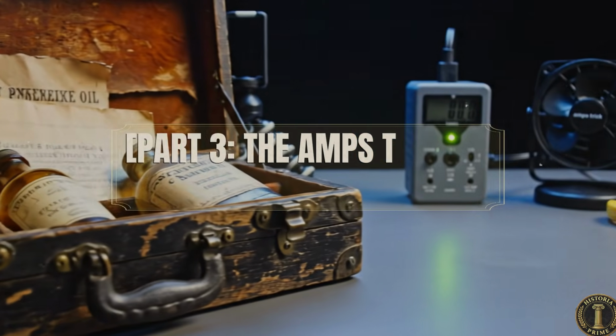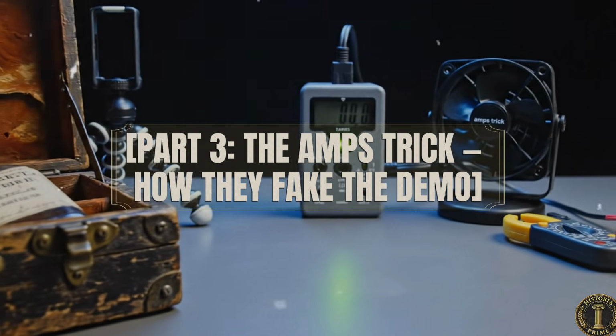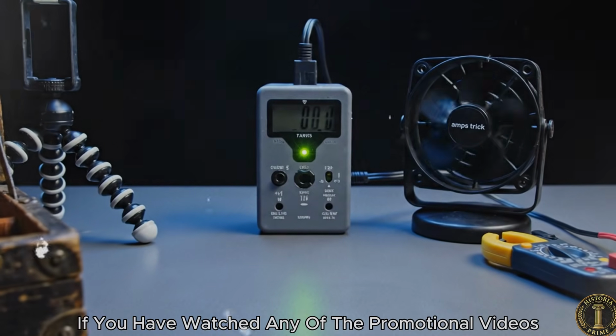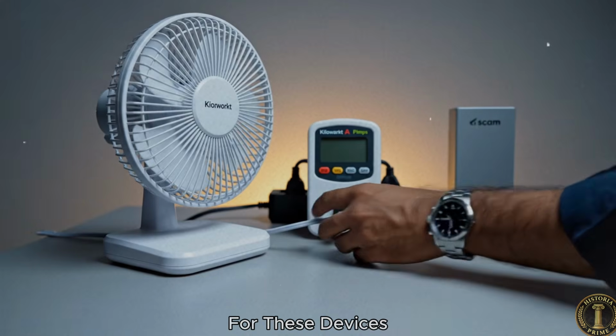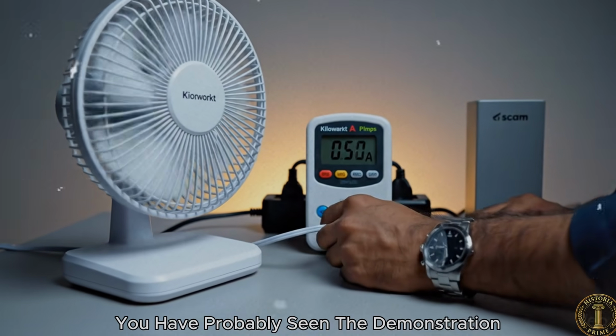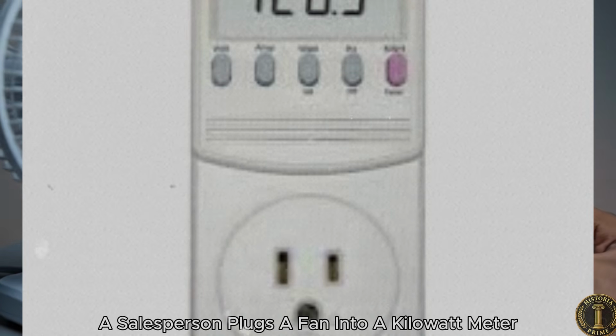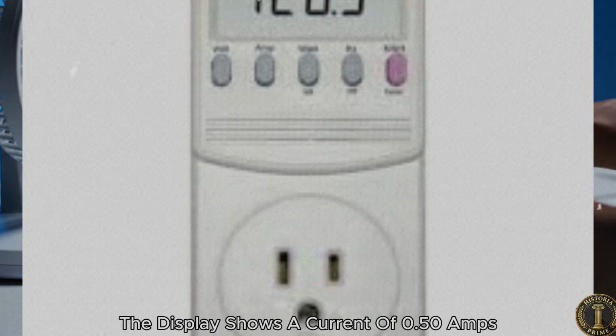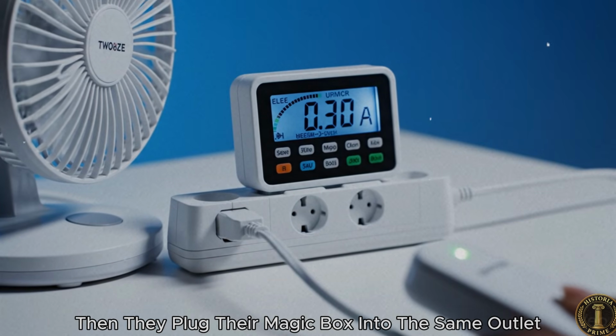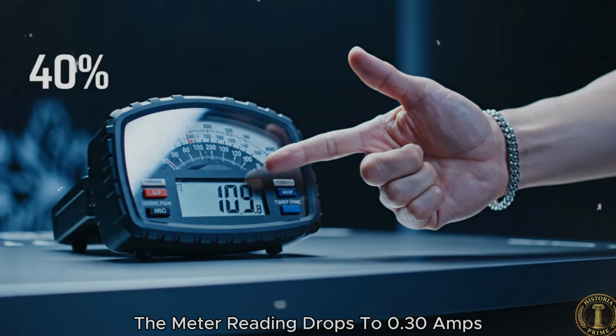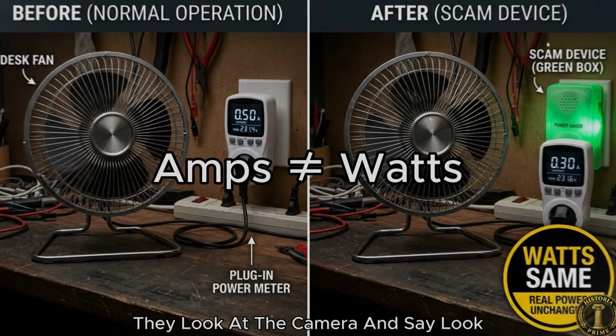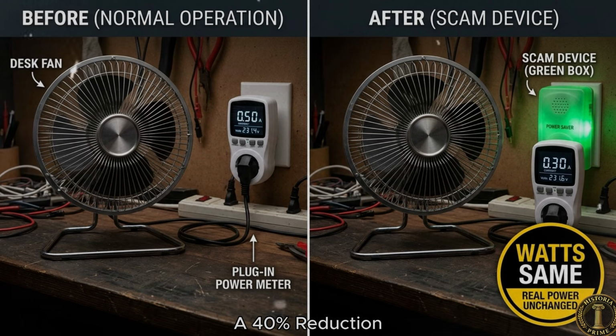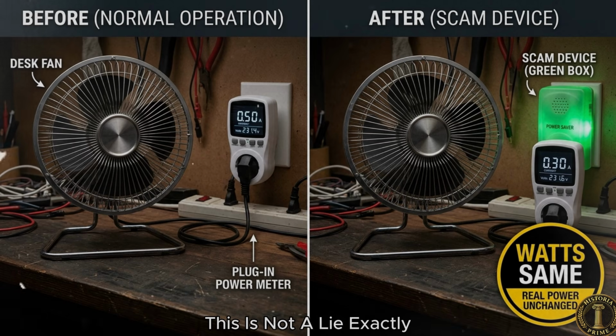Part 3. The amps trick. How they fake the demo. If you have watched any of the promotional videos for these devices, you have probably seen the demonstration. A salesperson plugs a fan into a kilowatt meter. The display shows a current of 0.50 amps. Then they plug their magic box into the same outlet. The meter reading drops to 0.30 amps. They look at the camera and say, "Look, a 40% reduction." This is not a lie, exactly.